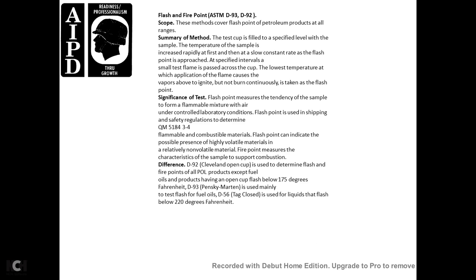Flash and Fire Point — ASTM D-93, D-92. Scope: covers flash points of petroleum products at all ranges. Summary: a test cup is filled to a specified level; sample temperature is increased at a steady, slow rate as the flash point is approached; at specified low intervals a flame is passed across the cup; the lowest temperature at which the application of a flame causes the vapors above the sample to ignite is taken as the flash point.